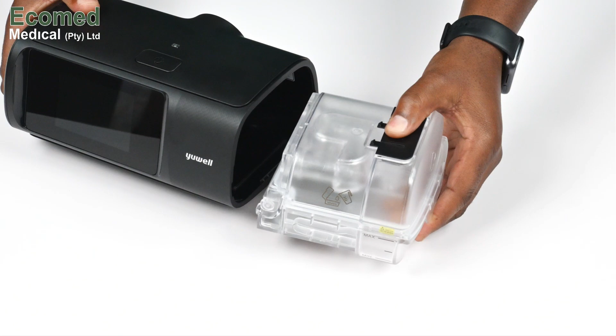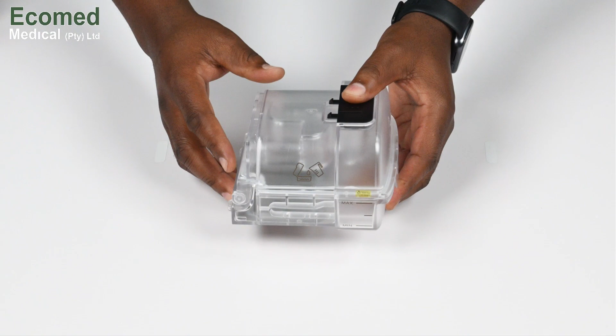The tank can easily be taken out by placing 2 fingers under the tank and by gently depressing the black plastic lever on the top of the tank with your thumb. It is important to take note of the maximum and minimum filling line on the tank. To open the tank, place 2 fingers under the clear plastic lip on the side of the tank and gently pull upwards. It is very important to use distilled water when filling your tank.